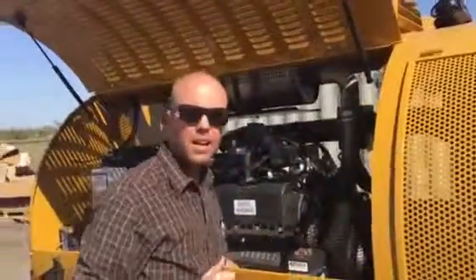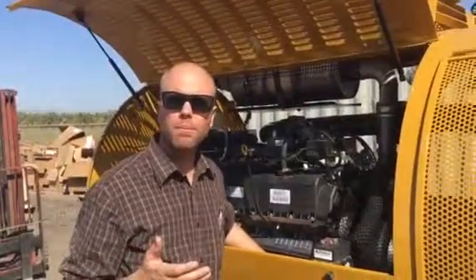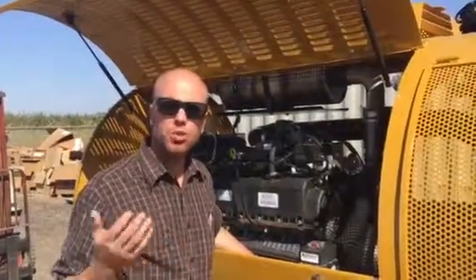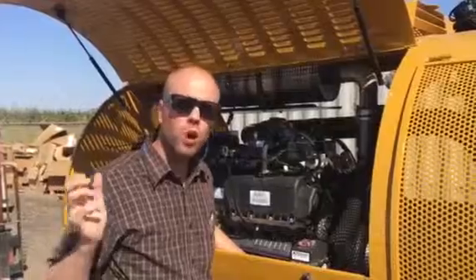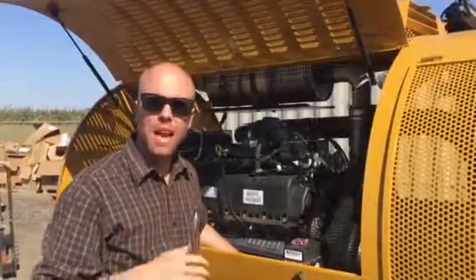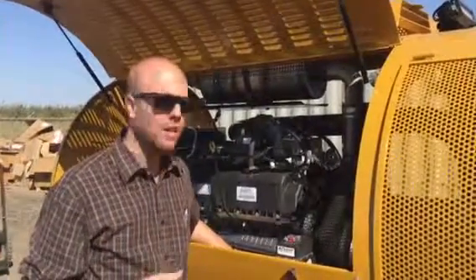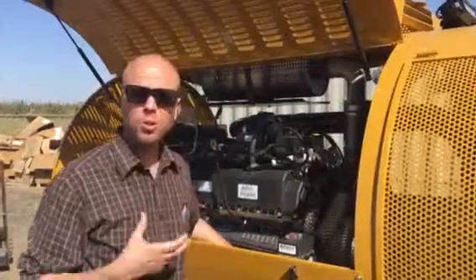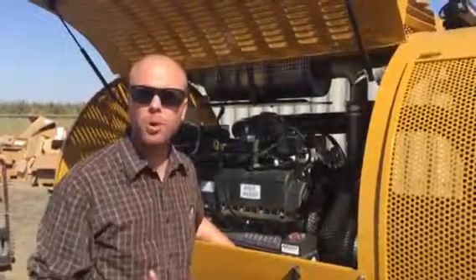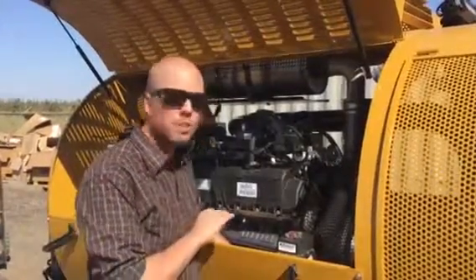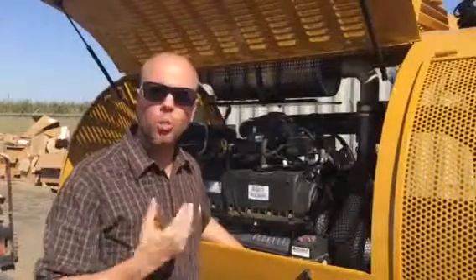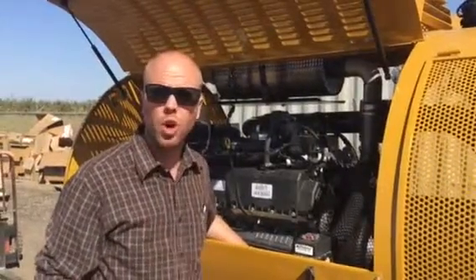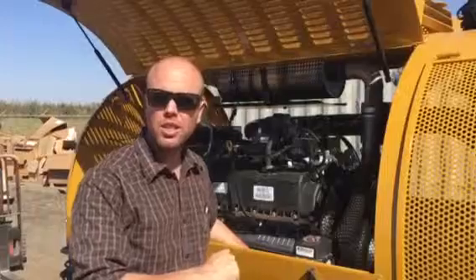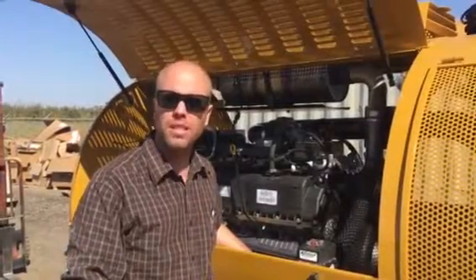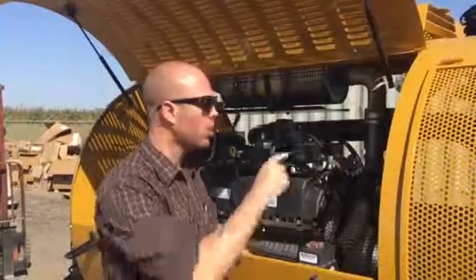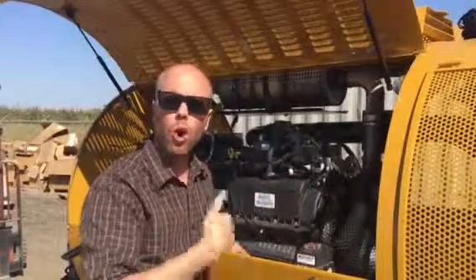The pump is a centrifugal pump. So what that means is it's using centrifugal force to force the water through the pressure plumbing system, and that's what's applying the pressure and the rate. Very high volume pump, 200 gallons or 100 gallons per minute. But the pump does require water flow through it. You don't want it to cavitate water, you don't want it to run dry. So don't let the clutch sit and idle for long periods of time. You either want to kick that clutch out or open that bypass valve and allow the water to flow through the system.